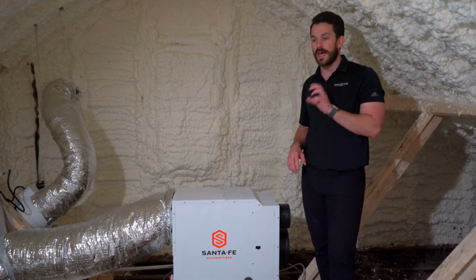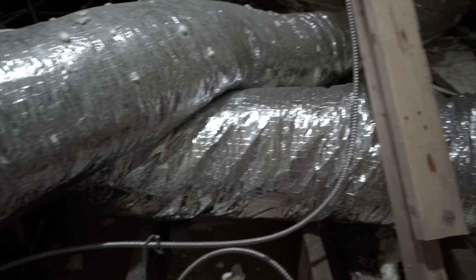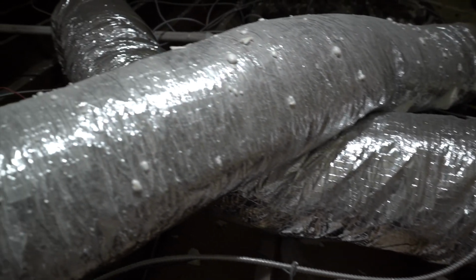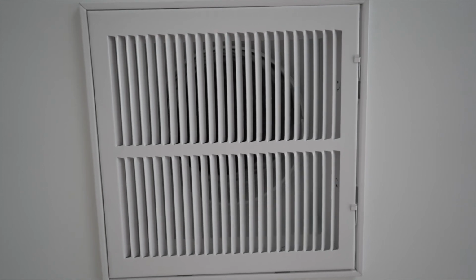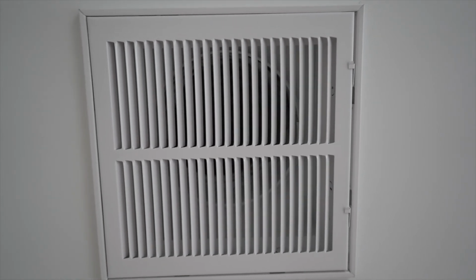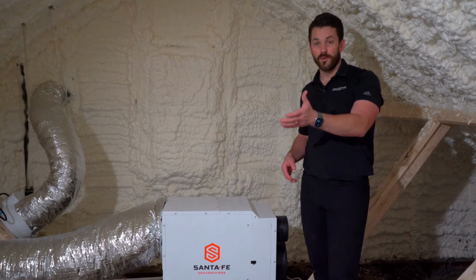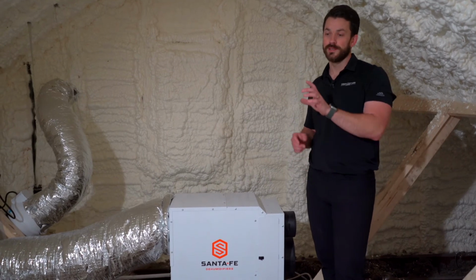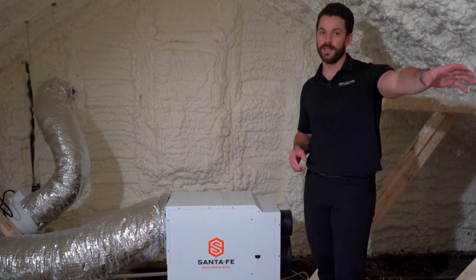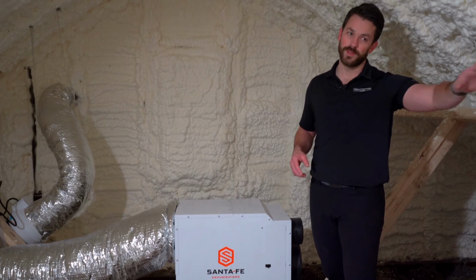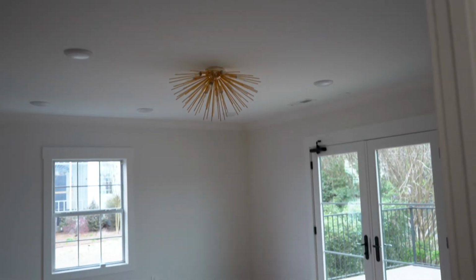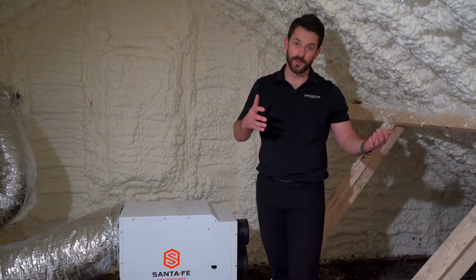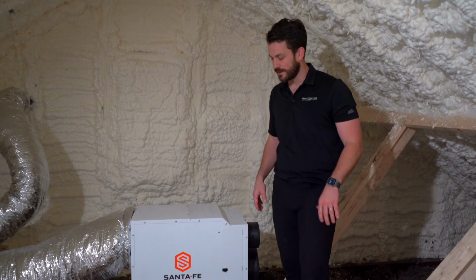One thing we've noticed is that having this pipe go to just one supply duct has made the two rooms down below unbalanced as far as temperature. So before we open this property, we're going to split that and add another supply duct across on the other side of the room, and in the adjoining room, to help balance out that airflow so we don't have a hotter and a cooler room. Again, more balance is the goal.